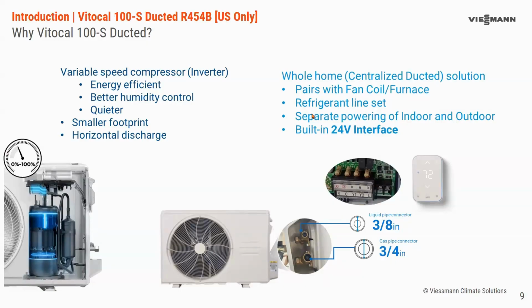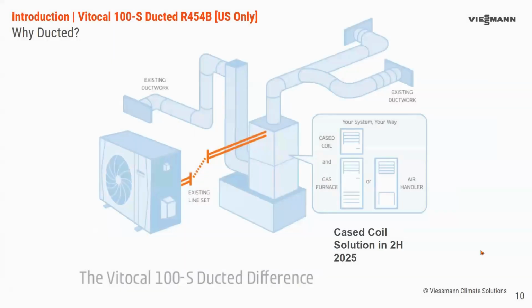It has a similar power setup as a ducted unit. So if using electric heat, you'll need your separate point of power at the indoor and the outdoor, as well as there's a built-in 24-volt interface in the indoor unit as well as the outdoor unit. So it gives you the flexibility. This system can be wired and communicate in different ways. So the takeaway is you get the larger line sets that match up to what's there today, and you can use any thermostat essentially.